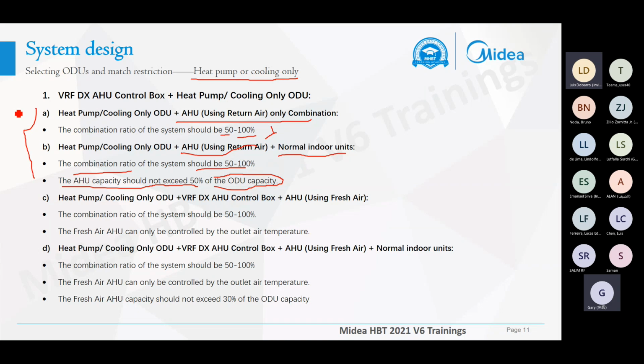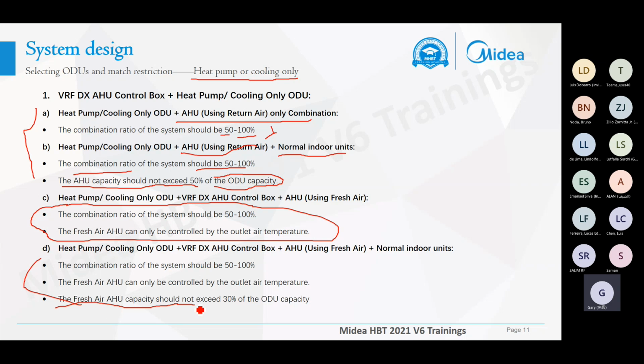This application is for the return air AHU. Now when the AHU is a fresh air unit, or you select fresh air control: the first one, the combination ratio when you only have DX AHUs, is the same. But when you use the fresh air control, the fresh air capacity should not exceed 30% of the outdoor unit capacity. This is one more strict rule when you use the fresh air control.